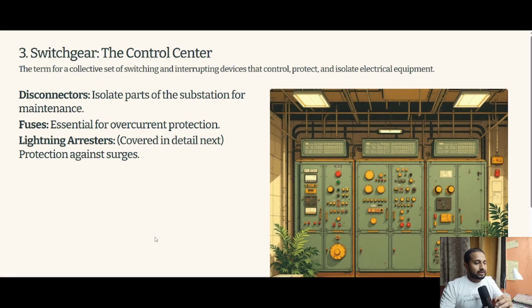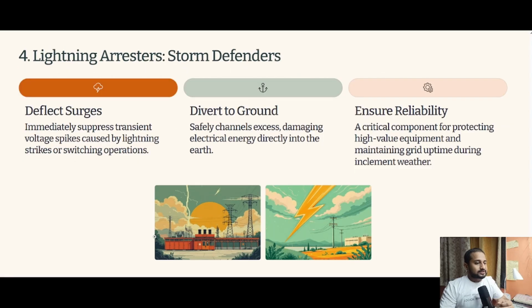And lastly, lightning arresters. Now the lightning arresters are storm defenders. They deflect the surges, immediately suppress the transient voltage spikes caused by the lightning strikes or switching operations. During lightning strikes or switching operations, the voltage level can go very high. So in that case, lightning arresters are used for protection of the equipment.